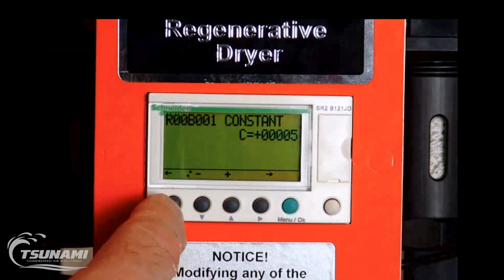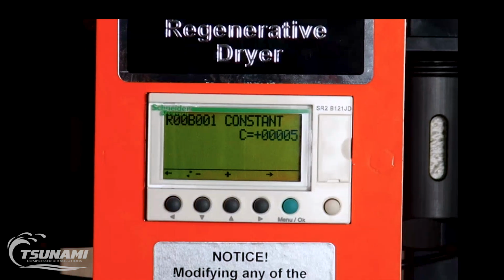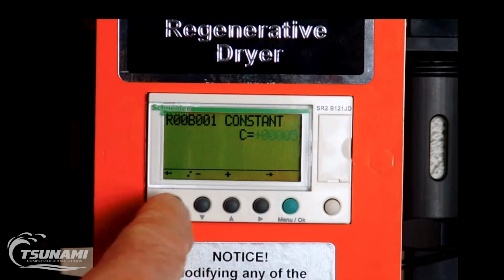So now what I can do is talk to you about some of the different blocks that are being utilized. If I move the left arrow over until block 1 is flashing and I hit the arrow up to block 2, block 2 has to deal with some of the settings that are going to come in. Some of our dryers are configured with a pressure transducer so that we can pull a signal from a compressor or from some piece of equipment that says it now has air, or does it have air.